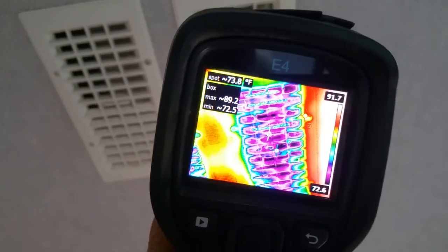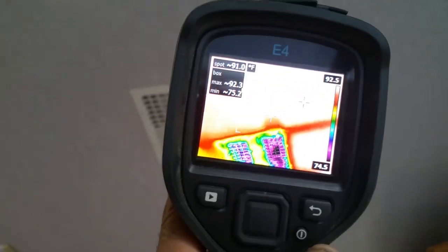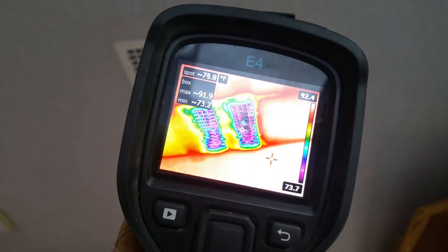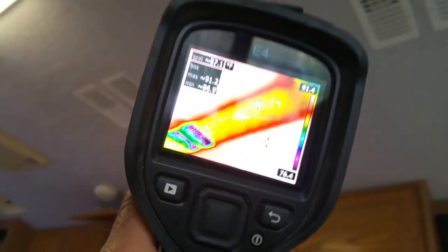You can see the pattern of the air coming out. It's 90 degrees out right now and it's putting out 74. As it's bringing it down, you can see that's the air — the ductwork going down the center of the unit. Here's another unit down here, the mid one.